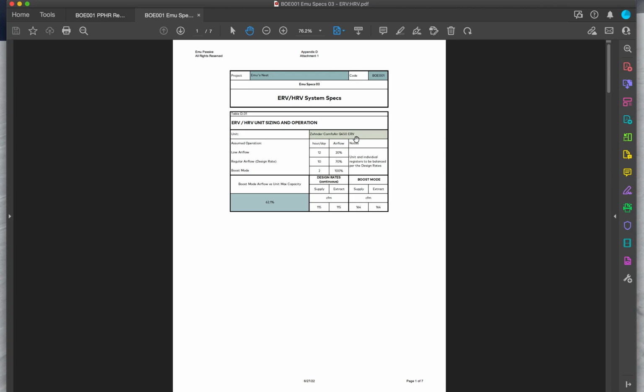We would make that recommendation as part of the modeling, as the outcome of the model. In the next table we're going to see the airflow rates that we spec for design, as well as in boost mode, so that you have the option to set the building in boost mode to get some extra ventilation if you need it.